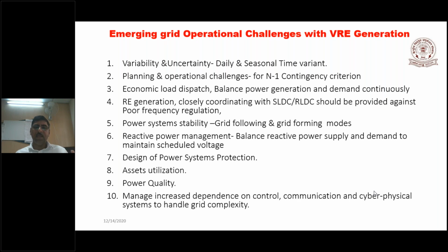What I mean to say is that this is only a two-area system I cited. If it's a multi-area system, there will be a continuous hunt for voltage control in the system. So it will be very challenging for the operator to manage the system voltage. And there's another issue. This will also give rise to reactive power management problems in the system.